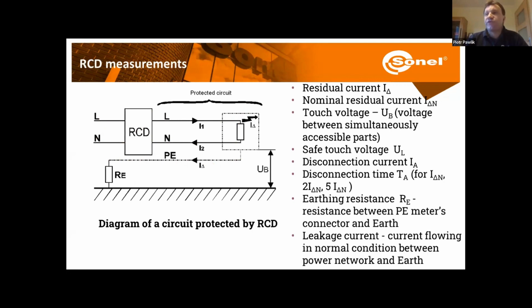So here, when we want to measure the parameters of the RCDs, we have the following parameters. We can check what is the residual current. We can check what is the triggering time for the RCD. And we can also check what the resistance to earth and touch voltage will be.